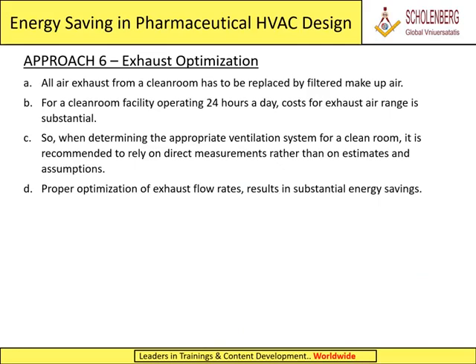Approach 6, Exhaust optimization. All air exhausted from a clean room has to be replaced by filtered makeup air. For a clean room facility operating 24 hours a day, costs for exhaust air are substantial. So, when determining the appropriate ventilation system for a clean room, it is recommended to rely on direct measurements rather than on estimates and assumptions. Proper optimization of exhaust flow rates results in substantial energy savings.